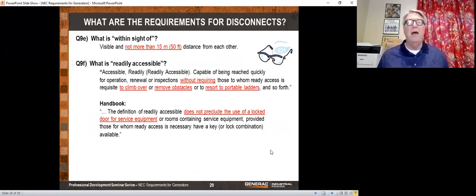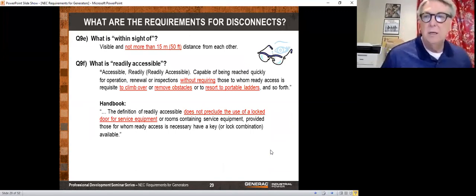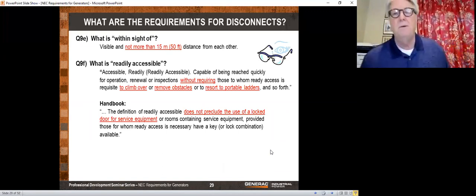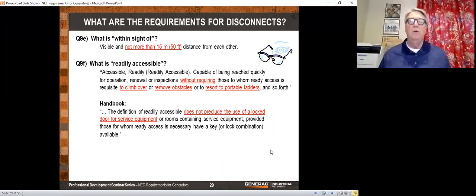I'll just say that. What does within sight of mean? It means visible and not more than 50-foot distance. So you got to be able to see it, and it can't be more than 50 feet. We will talk about that a little bit more in a minute. Now, readily accessible means capable of being reached quickly for operation, renewal, or inspections without requiring those to whom ready access is required to climb over and remove obstacles or to resort to portable ladders.